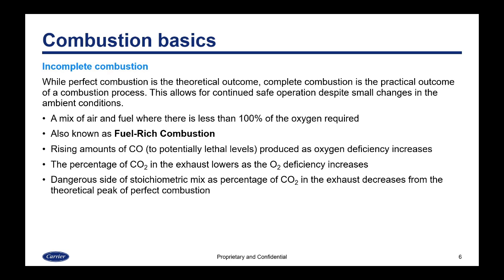Incomplete combustion is the opposite. This is where the mix of air and fuel is less than 100 percent of the oxygen required and is also known as fuel-rich combustion. A rising amount of CO to a potentially lethal level can be produced as the oxygen deficiency increases. The percentage of CO2 in the exhaust also lowers, same as with complete combustion, except that as the CO2 percentage decreases you are on the dangerous side of the stoichiometric mix.